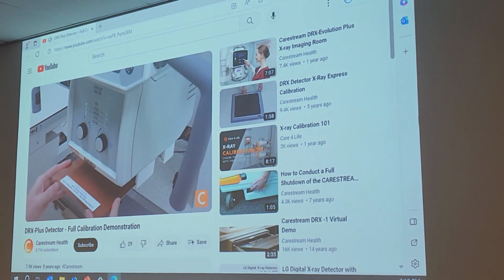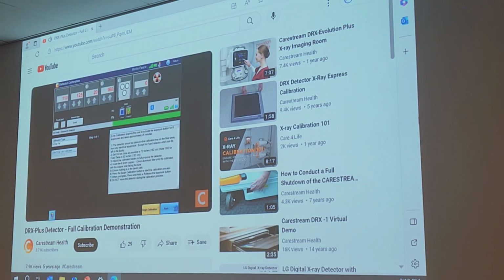Ensure that there is nothing in the beam path, such as a lead marker that may have been left on the detector. Press the Begin Calibration button to start the calibration process. This will be an 8-step process and will take approximately 20 minutes to complete. Several steps will require no interaction by the radiographer. When prompted, acquire an image using the Prep Expose button as normal.